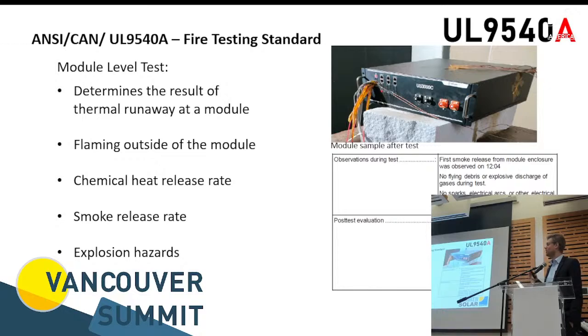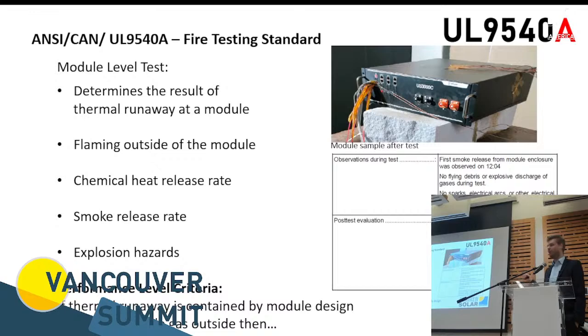For example, you cannot have any flaming outside of that module. You cannot have a certain heat release, so it cannot be extremely hot what the module is radiating to it. There's also a chemical release or heat release rate where certain chemicals are being released that cannot or should not go up in flames. The smoke needs to be limited to a certain amount of volume over a certain amount of time, and the whole thing cannot explode. Once you have contained all those risks, then you can pass the performance criteria on the module level.